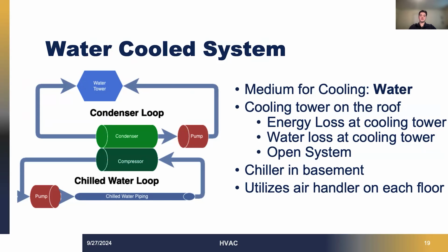For larger HVAC systems, a water-cooled system with a chiller, as shown in the center of the picture, is often ideal. This system integrates the refrigeration cycle we discussed earlier with a secondary and tertiary water loop to effectively cool the building. Water-cooled systems are more complicated and designed to handle higher cooling loads, making them suitable for demanding applications. Additionally, they require air handlers on each floor, which can increase installation and operational cost.